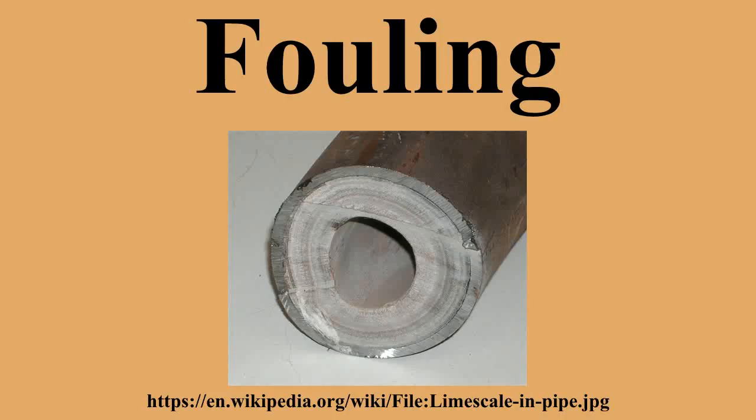Linear fouling. The fouling rate can be steady with time. This is a common case. Falling fouling. Under this scenario, the fouling rate decreases with time, but never drops to zero. The deposit thickness does not achieve a constant value. The progress of fouling can often be described by two numbers: the initial fouling rate and the fouling rate after a long period of time.